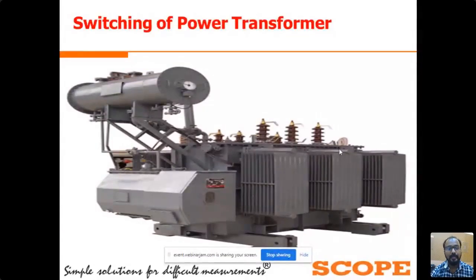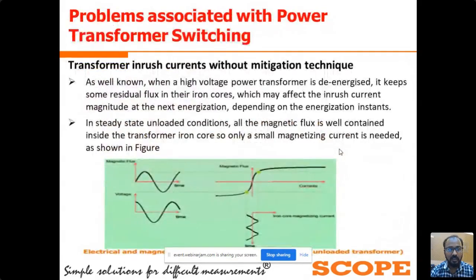Now we will see the control switching device for the power transformer application. As we all know, the main problem associated with random switching of a power transformer is the high inrush current during the no load energization of the power transformer. That means whenever the secondary side is open and we energize the power transformer without any load, we have observed a very high inrush current in the power transformer.